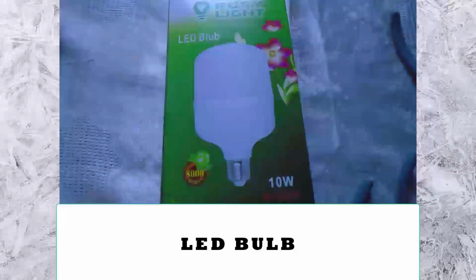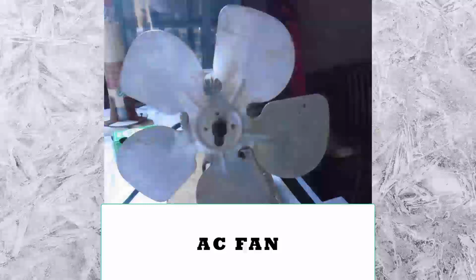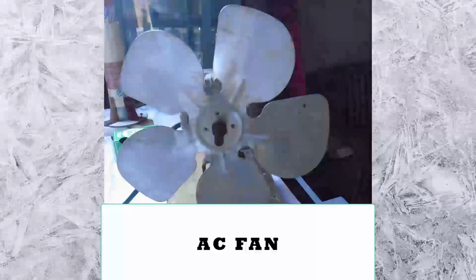This type of bulb should not emit heat because if you forget it after turning it on, it will not constitute a risk of overheating for the incubator. Its role is only to allow viewing from the inside without having to open the incubator. Over-opening an incubator can cause inconvenience in the incubation process. A fan that works in 220 volts because the thermostat works with alternating current. You should pay attention to the kinds of components you use depending on your thermostat model.